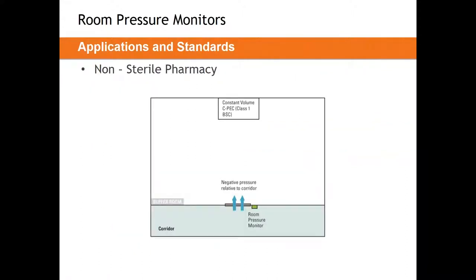The first pharmacy layout is a non-sterile compounding pharmacy. No anteroom is required, so we go directly from the corridor into the buffer space. This is a negatively pressurized space with 12 air changes per hour and a room pressure of minus 0.01 to minus 0.03 inches. Inside you'll typically find a Class I biological safety cabinet. Placement of the room pressure monitor and sensor are practically identical to isolation rooms — right beside and above the door.